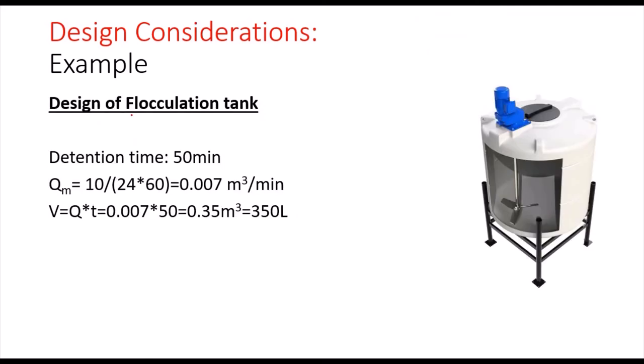Now concerning the design of the flocculation tank, we have chosen a detention time of 50 minutes. We will convert the flow from cubic meters per day into cubic meters per minute to be consistent. So it will be 10 divided by 24 times 60, and we will get 0.007 cubic meters per minute. Concerning the volume of the flocculation tank, it will be V equals Q times t, 0.007 times 50, which is 0.35 cubic meters or 350 liters.